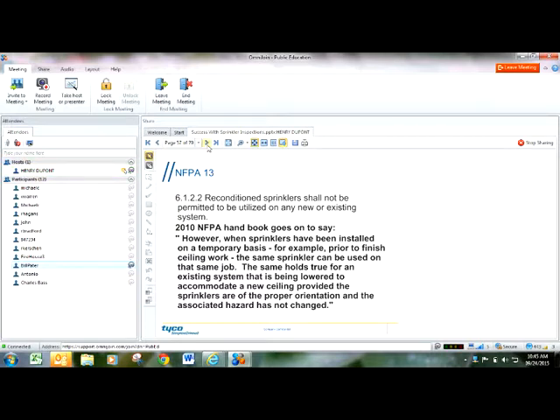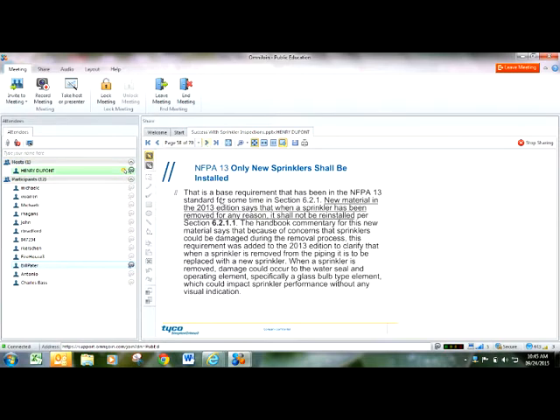Well, since that was a little vague, the 2013 edition of NFPA 13 came out and they said it bluntly. If you take a sprinkler head out for any reason, you've got to put a new one back in its place.